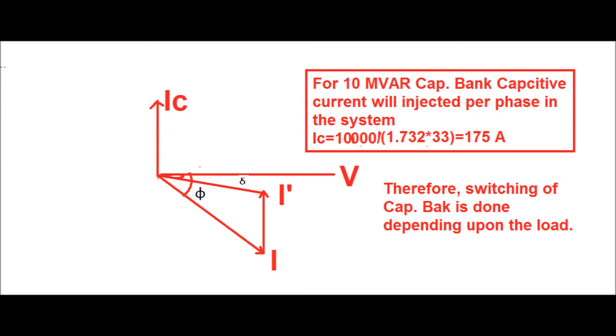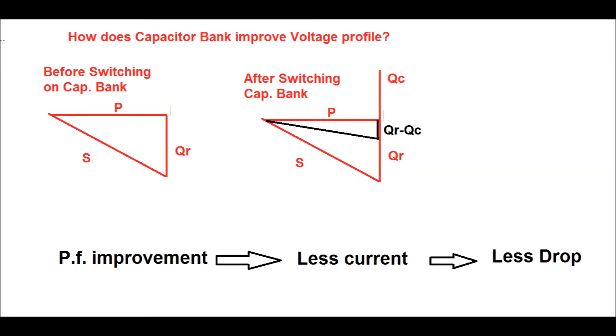Switching of the capacitor bank is done depending upon the load. Mainly in substations, switching is done during peak load periods, when most of the lagging power factor load is nullified and the power factor is improved. Before switching the capacitor bank, QR is the reactive power of the system. After switching on, the reactive power becomes QR minus QC, where QC is the leading reactive power injected by the capacitor bank. Since the power factor is improved, less current is drawn from the system, reducing line losses and voltage drop, which automatically improves the voltage profile.